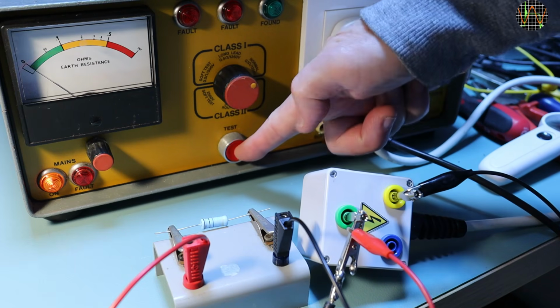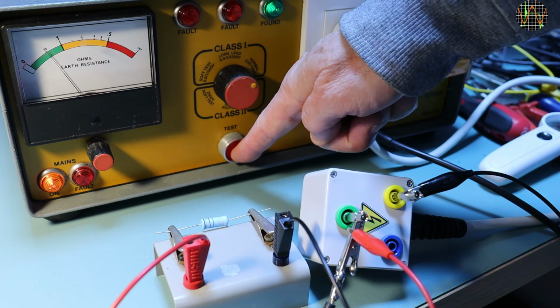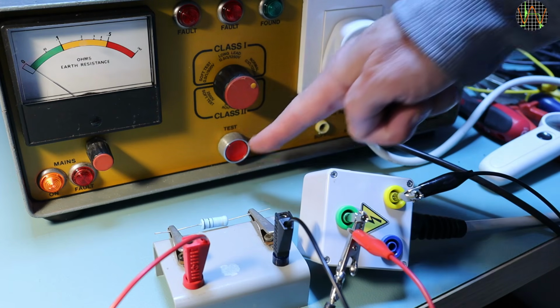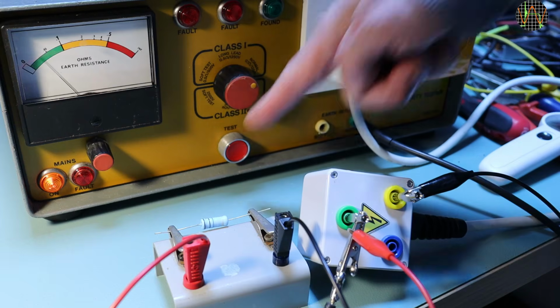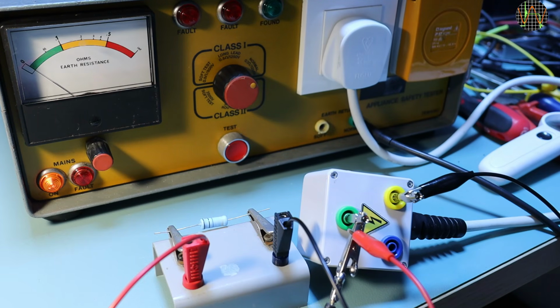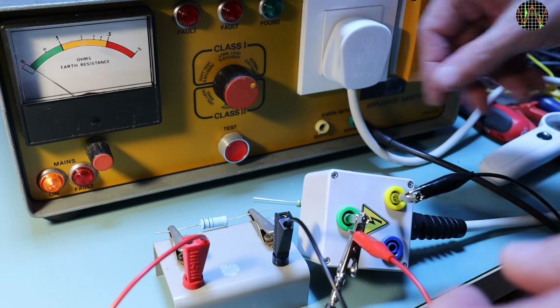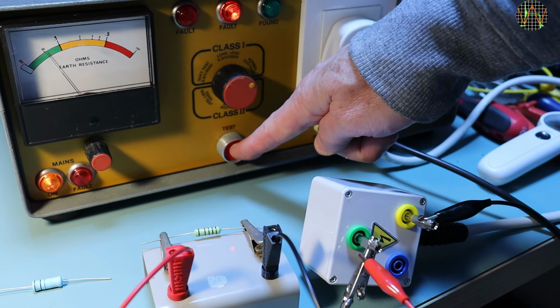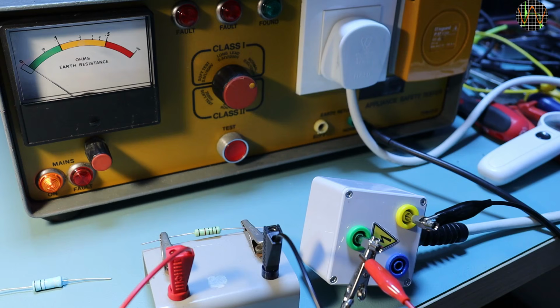Of note, there are no trim pots to compensate for the somewhat indeterminate relay thresholds. This means the insulation tests can only be a rough guide. To test what the unit will pass in class 1, I connect a fixture with a 10 meg resistor between live and earth. This is where the high voltage will be applied in a class 1 device. Okay, it passes. 10 meg is sufficiently high. How about 10K? That should fail. And it does. So insulation testing does work.